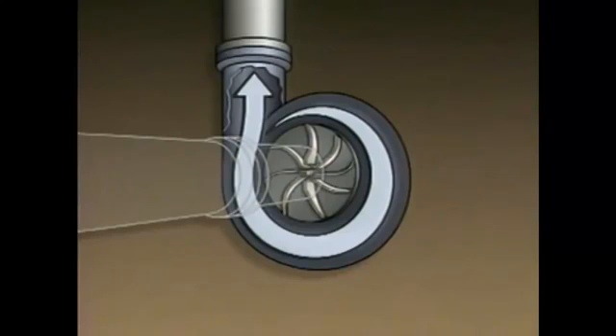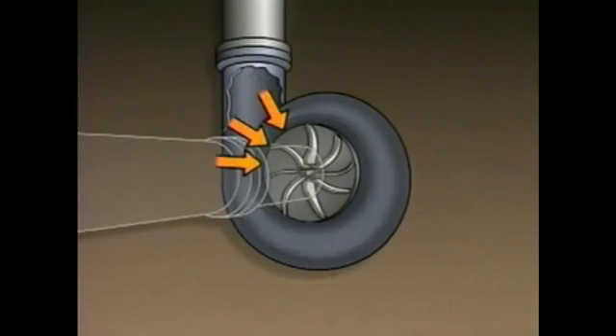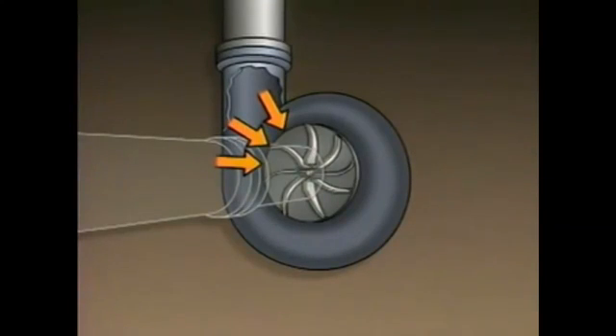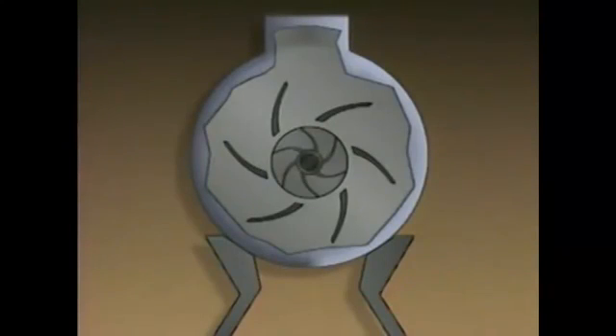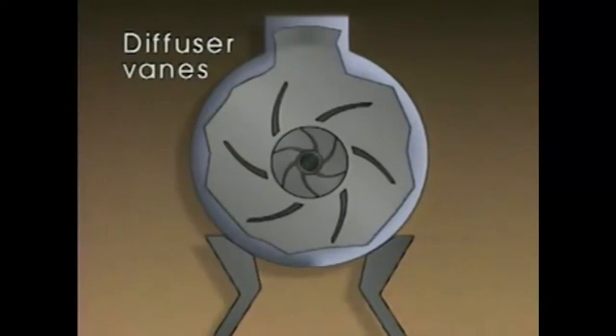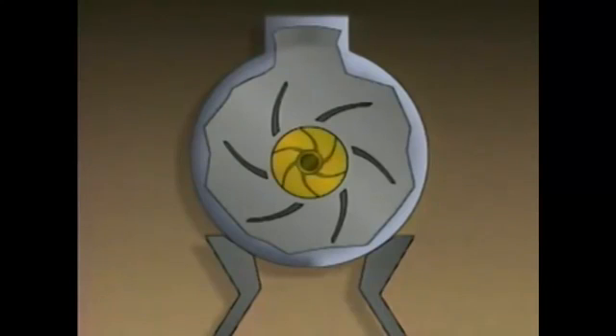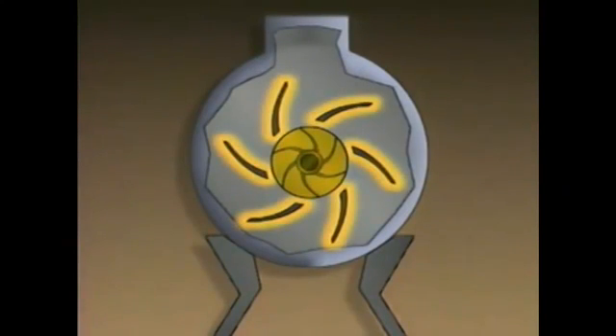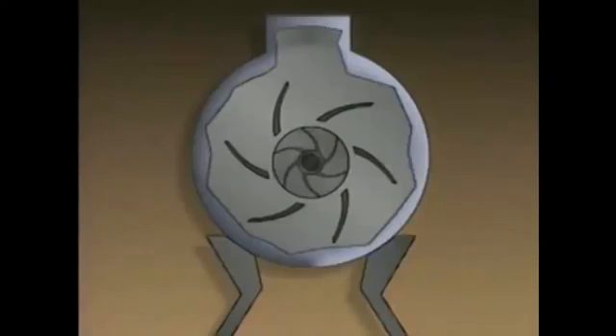In a compressor with a volute, the gas in the volute creates a force called radial thrust, which tends to push against the impeller. Radial thrust is created by the difference in pressure that the volute creates from one side of the impeller to the other. Some centrifugal compressors are designed to minimize radial thrust by using a series of plates or vanes called diffuser vanes. In this type of compressor, the impeller is surrounded by the stationary diffuser vanes. The distance between the outer tips of the vanes is greater than the distance between the inner tips, and the vanes create a series of small volutes all around the impeller.